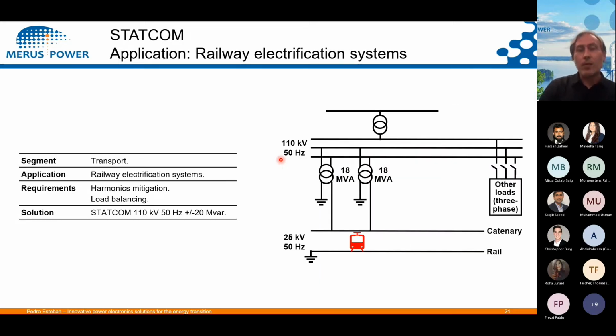And finally, another application example in medium voltage will be railway electrification systems. Railway electrification systems have two issues here. One of the issues will be harmonics, because of the rectifiers in the locomotives, in the trains. And the second issue will be load balancing. This is a big thing, because you see in this diagram a typical connection of this railway electrification system. We are taking power from 2 phases in a 3-phase system. That means that we are creating unbalance.